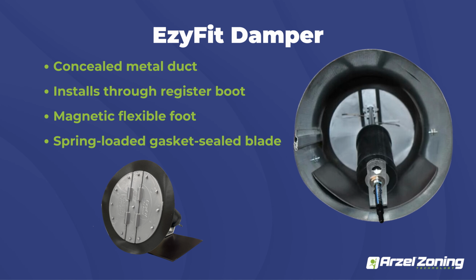That magnet's going to hold it in place, and then when you let go of the blade, everything springs back open. And that damper's got a nice gasketed seal as well, so you don't get the bleed by, you don't get the drawbacks of the register-style damper, but you're still able to access these right at your register. So if they do finish that basement and they ever have a failure, you guys don't have to worry about mapping the basement, busting drywall, trying to find the dampers. You can literally go to the register itself, pull your damper right out of the register and replace it that way.